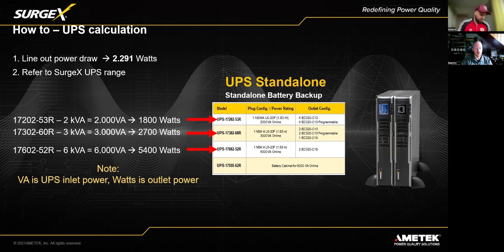Ours are very good, with a power factor of 0.9, meaning you invest 1000 VA and get 900 watts out of it. That's quite important for sizing the UPS, and it's also where the equation sometimes gets mixed up. By the way, that's true for every electrical product - you always need to invest slightly more energy to get a result out, whether it's an electrical motor, a UPS, or any other electrical equipment.